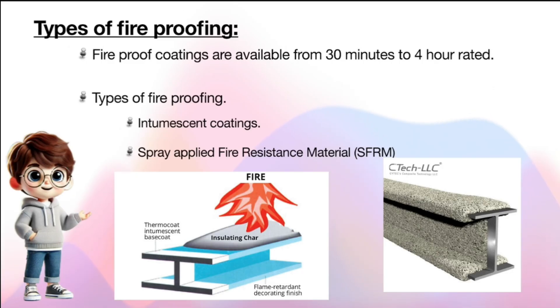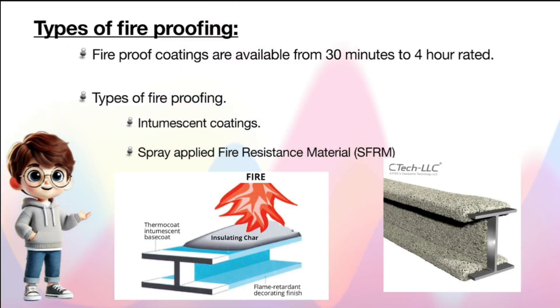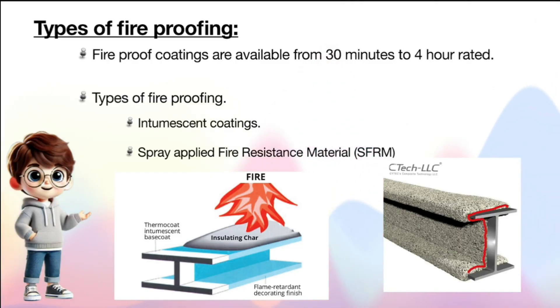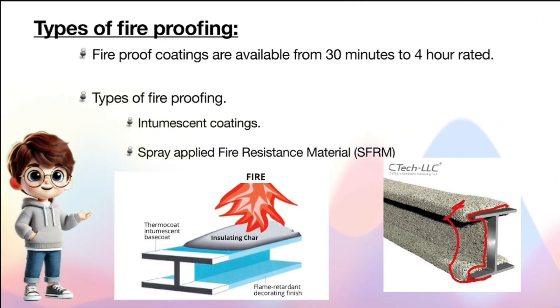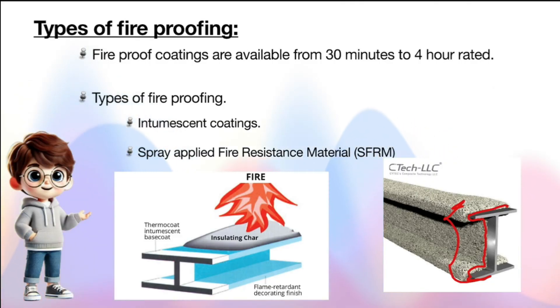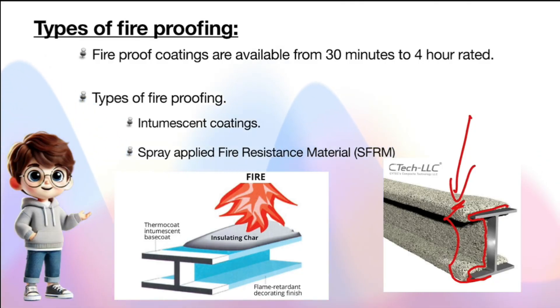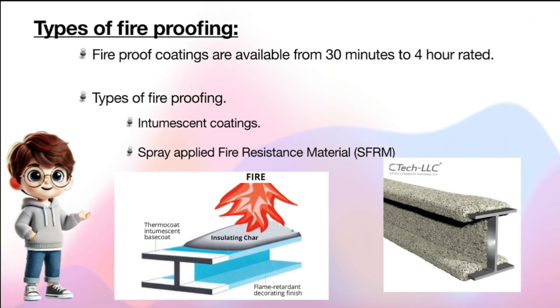For spray applied fire resistance material, we apply a layer of cement slurry with high pressure jets on the surface of steel. This is very cost effective, but the main disadvantage of this type of coating is that the weight of the member will also be increased with this coating.